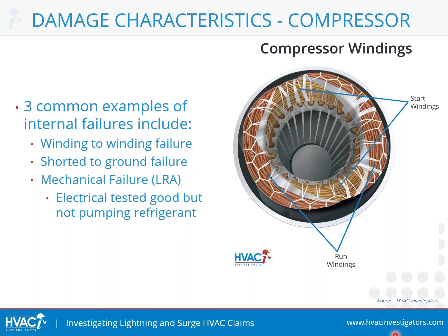The last one is mechanical failure. In this particular case, LRA stands for Locked Rotor Amps. That means all the electrical tests came back good — we don't have any electrical issues — but the compressor is not pumping refrigerant. It's not moving. So what could cause that?